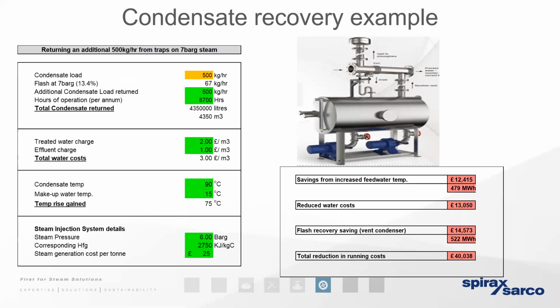So we can calculate its financial value, and we can calculate if or where that condensate can be reused elsewhere in the plant. And if we can't reuse that flash steam elsewhere, then maybe we can condense as much of it as we can and return that liquid condensate back to the pump, thereby increasing the condensate rate. And if we know the mass flow of condensate that we can now increase and get back to the boiler house, then if we know the cost of steam, the cost of water, the cost of fuel and chemicals, then we can demonstrate an attractive payback for our clients.